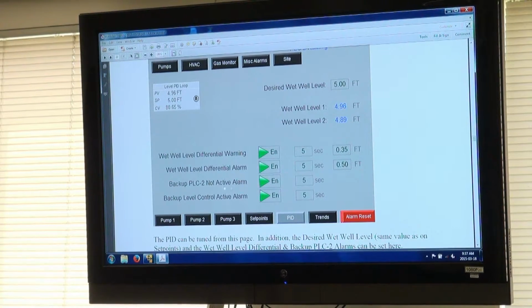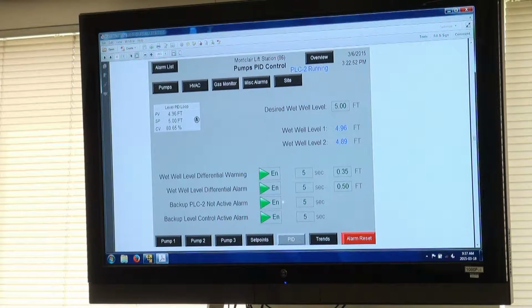We also have PLC 2 not active. If PLC 2 is not active, that means it's not running in the background. It's not going to back you up if something happens to PLC 1. Then you have PLC 2 is in control. That means PLC 1 has stopped running and now PLC 2 is in control. It's taking control of all the pumps.